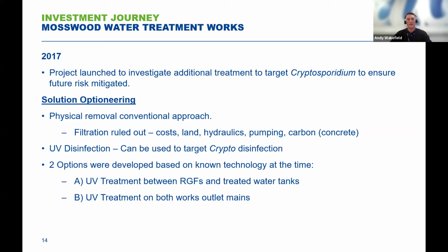So adding an additional filtration stage or modifying the existing filtration stages. To do this, we looked at potentially adding an additional filter to the process, a granular activated carbon plant. But this was ruled out due to the high levels of cost associated with doing so. The project would require the purchasing of land. It would alter the hydraulics of the site.